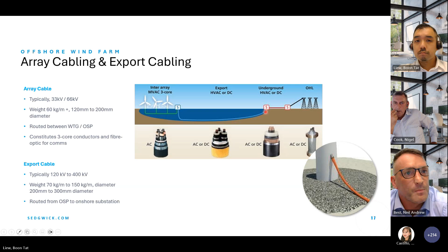Okay, next slide. So after the inter-array cable leaves the string of the wind turbine generators, it enters the offshore substation platform to another set of switchgear. And the job of the station is to take the inter-array voltage, which we said before is 33 or 66 kilovolts, and transform that into the export cable voltage, which is typically between 120 and 400.